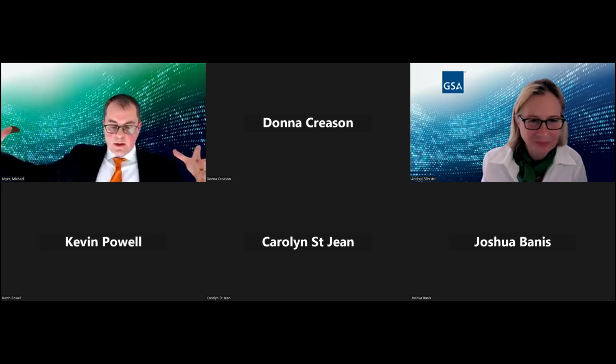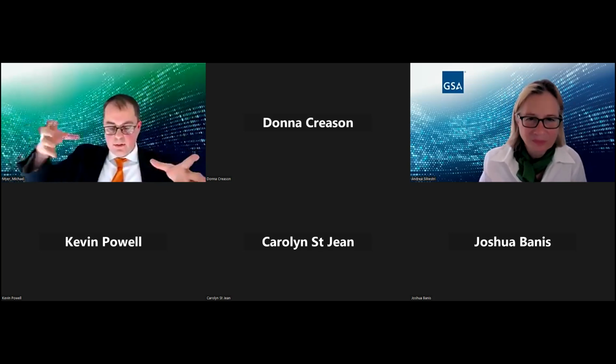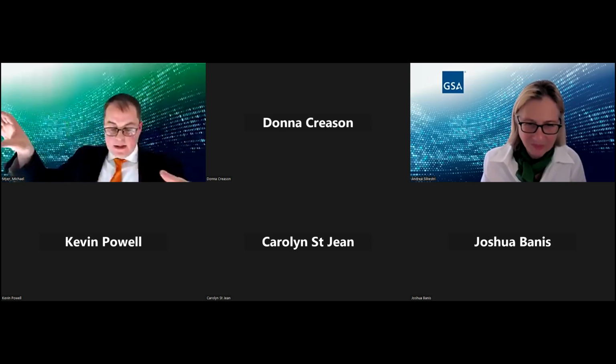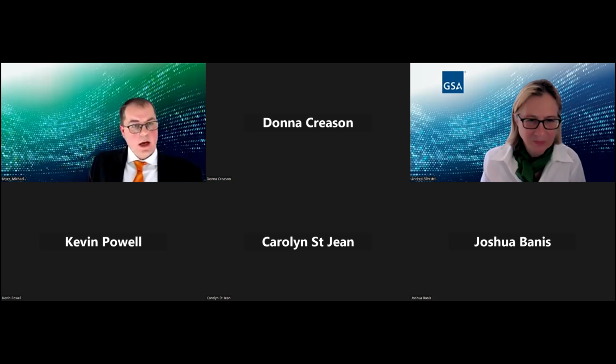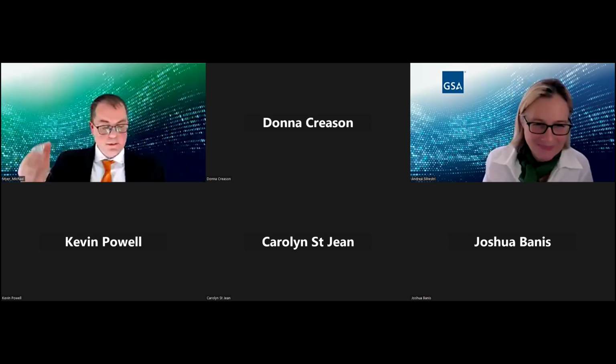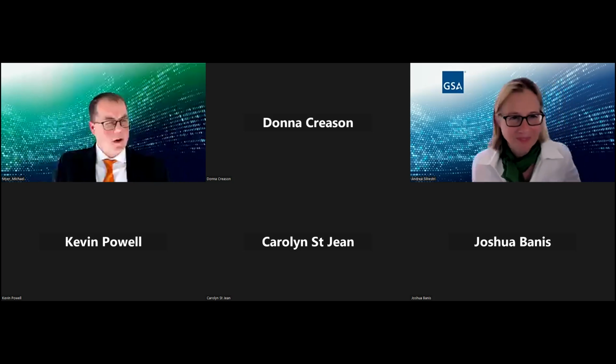Do you think for demand response you can couple zone lighting control with task lighting for more granular control? In a zone-based system, say 8 fixtures controlled by one control point, and you're bringing in demand response, ideally you have some means of telling those fixtures to dim, because that's what demand response needs. You could offset some of the reduction in lighting with task lighting, as this person may be asking, just as long as you're not increasing your plug load, which would reduce your demand savings. That's a little more complex, I think it requires a layout.